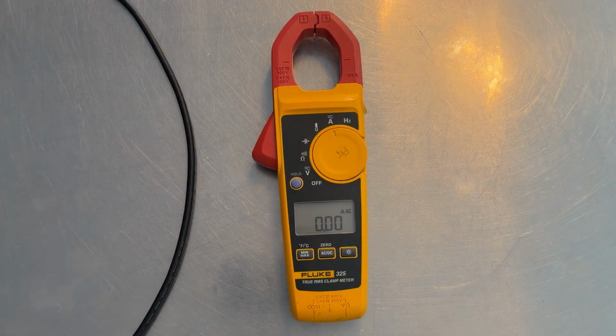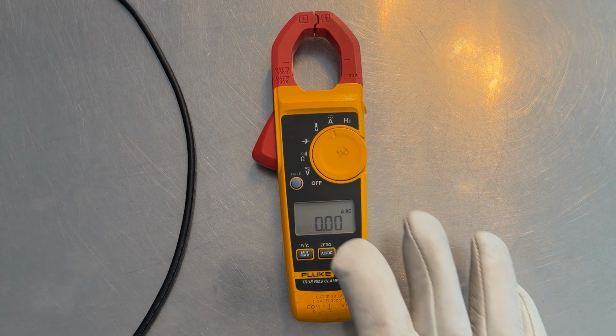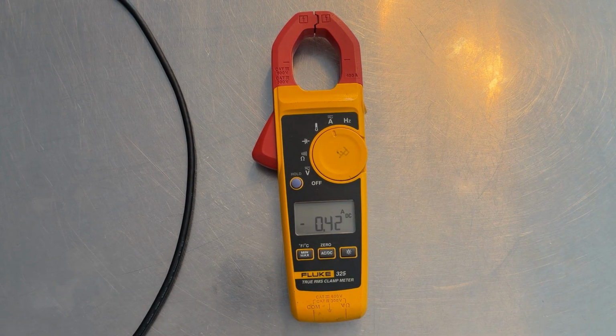Cut. Let's talk about zeroing out our multimeter real quick. When a clamp-on ammeter is attempting to measure alternating current, it's looking for the unique electromagnetic field that AC creates. So there's no need to zero it out. When it's attempting to measure direct current, it's picking up all of the static electromagnetic fields in the environment.